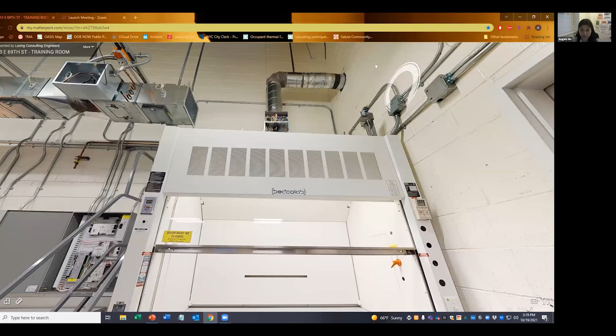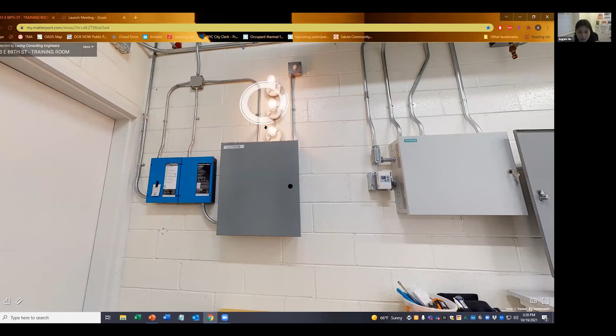We also did lighting. The most complicated lighting system on our campus is a Lutron Quantum system, so that's what we installed here. We have two rows of lights, one linear and one 2x2; one set is on a simple relay and the other is dimming capable. There's also an occupancy sensor connected to the lights, and everything connects to the Lutron panels and can be fully programmed. We've got bulbs and porcelain holders that simulate daylight for the daylight sensor, and in the corner we have an operable window shade. So we pretty much have one of everything.